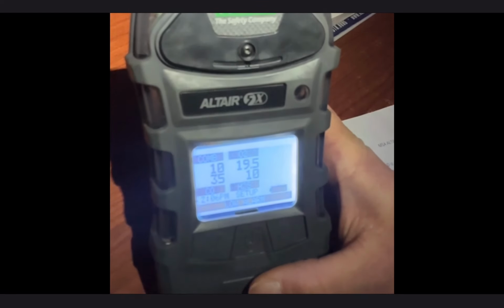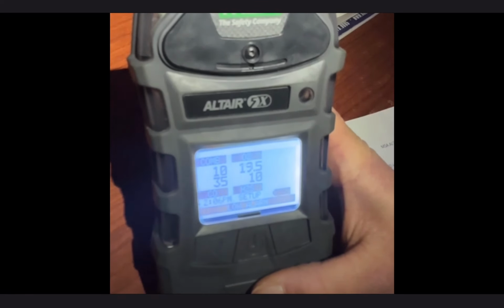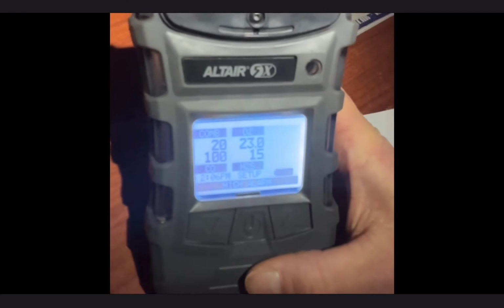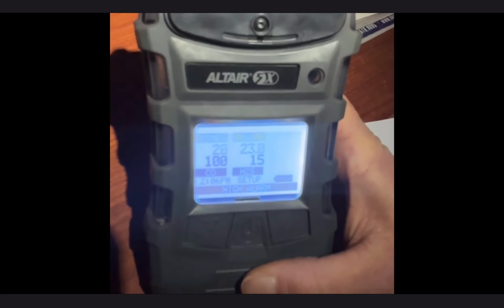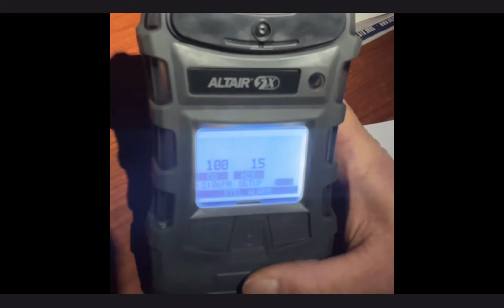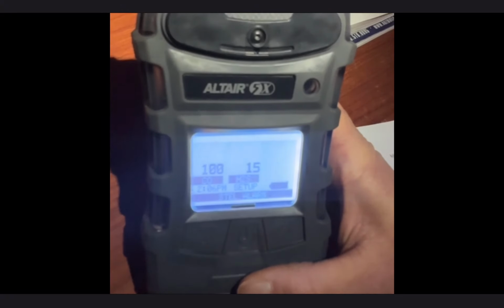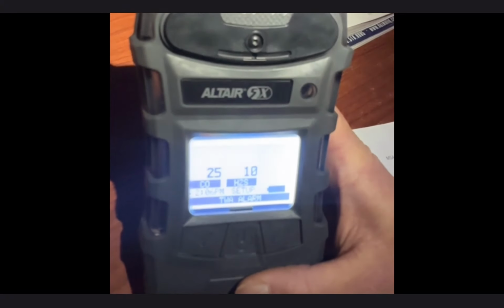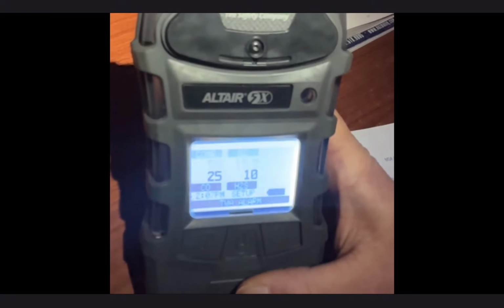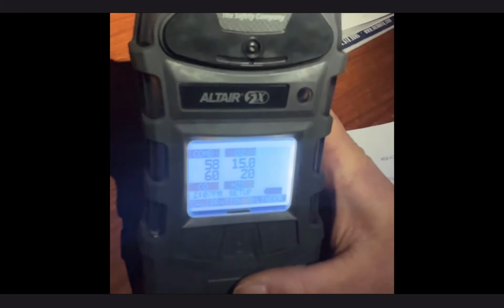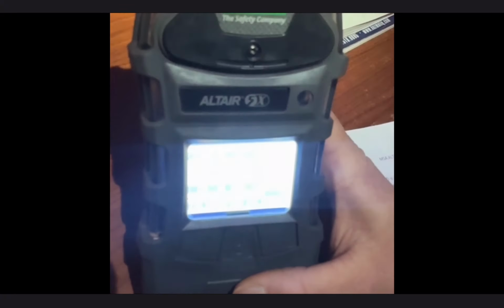So it's going through the 4 different types of sensors. It's going through the lower alarms, the upper alarms that we just talked about, the limitations of what they're set at, short-term exposure limits, time-weighted averages, and those are all in here as you cycle through. We'll go through that. It's going through what it's calibrated off. We use a pentane blend mixture, which uses methane for the combustion part, and the rest of the mixture to measure the limits within.